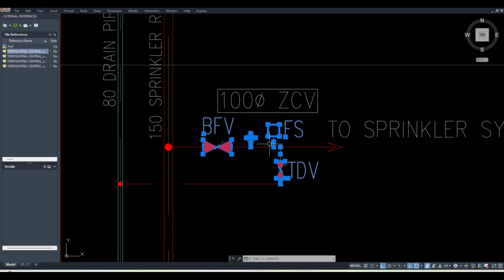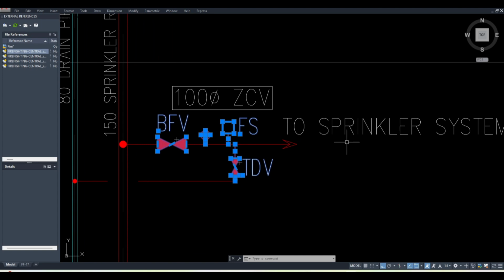Okay, then it has to be indicated, like below, one nameplate should be there saying this is a zone control valve. That is a requirement. Then this zone control valve and this flow switch, this whole arrangement has to be within 600 mm. So you cannot have the butterfly valve here and your flow switch somewhere 1 meter away, or the pressure gauge 2 meters away. You cannot have that. All these installations must be within 600 mm of space. And the combination of all these arrangements we call the zone control valve. And that zone control valve, you cannot hang it somewhere in the riser, somewhere where people cannot reach.